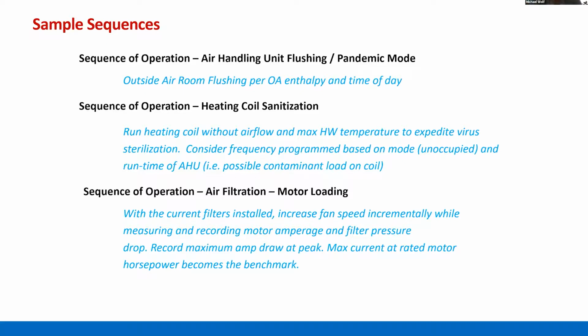Yeah. So I saw a question too asking about what type of sequences of operation and changes we have seen. Certainly a purge mode, looking at purging the spaces. I've seen 2 hours before occupancy being utilized. We're working on some commissioning projects right now that are new construction, but still in the design phase, with healthcare facilities, looking at whether we can get that protective environment and airborne infection isolation to be more of an ambidextrous room, where maybe there are bypass dampers implemented, different fans, essentially investing in the capital infrastructure to think about that next pandemic. So I am seeing that being taken in effect.